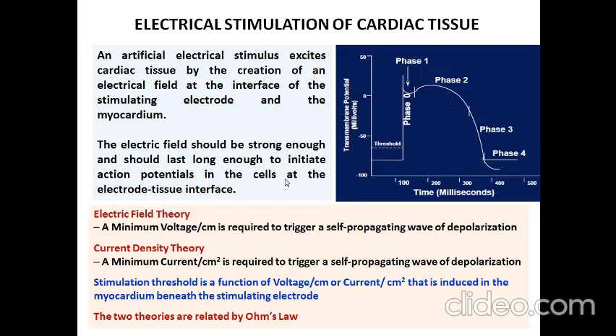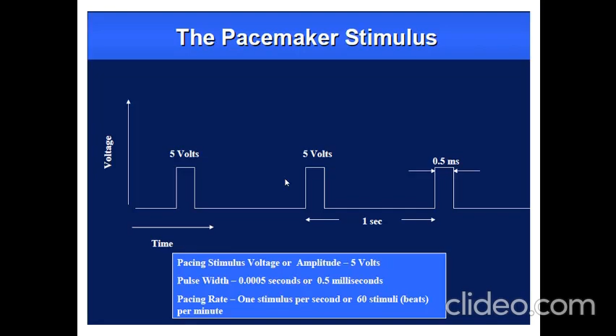Likewise, the stimulation threshold is a function of either voltage per centimeter, regarding the electric field, or current per centimeter square, regarding the current density, which is useful to excite the myocardium beneath the stimulating electrode. So these two are related to Ohm's law only. That's why we have the concept of impedance in a pacemaker. So just notice the pacemaker stimulus. We need an amplitude of at least 5 volts, and we are working with a pulse width of at least 0.5 milliseconds. The pacing rate should be 1 stimulus per second, meaning 60 stimuli is 60 beats per minute, a common pacemaker stimulus we use for improving cardiac activity.